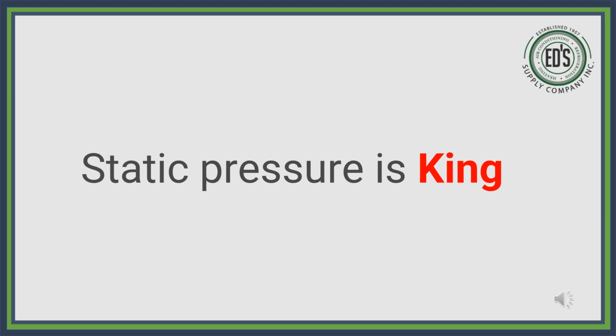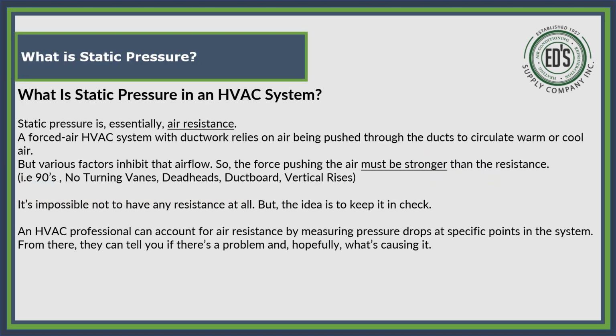And welcome to another video that we're going to be showing you this week on static pressure. Why is static pressure so important? Why is static pressure considered to be king? Well, static pressure controls everything, and it is something that is very sensitive and something that every unit needs to have set up and tested, no matter if it's a brand new install or an existing unit.